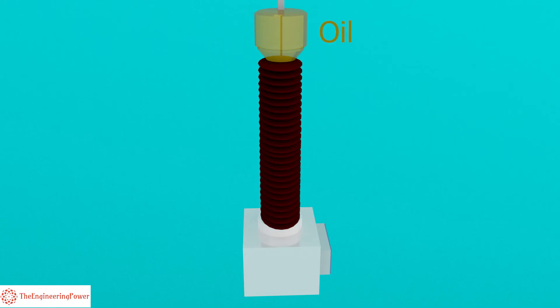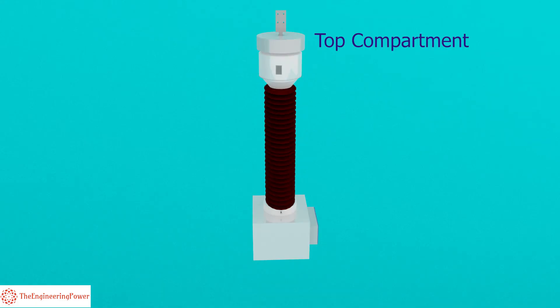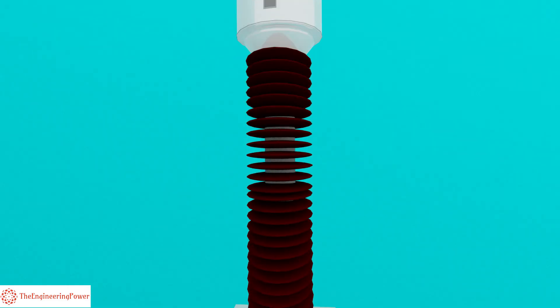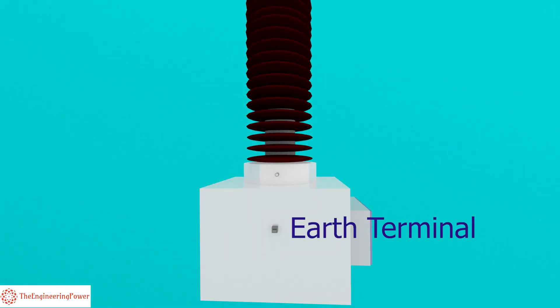The PT is filled with oil for insulation and cooling purpose. The oil can expand due to high temperature and load. So an extra compartment is provided at the top to accommodate the expansion of oil. The body of PT is grounded using an earth terminal at the bottom.